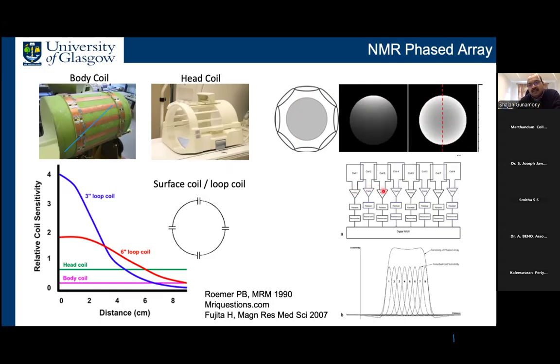So then the signals from these coils are amplified, then down converted and mixed and so on, and then digitized, and then we get a combined signal. So in this plot here, you can see the sensitivities of the individual coils, and then the combined sensitivity, which is higher than the individual sensitivities.